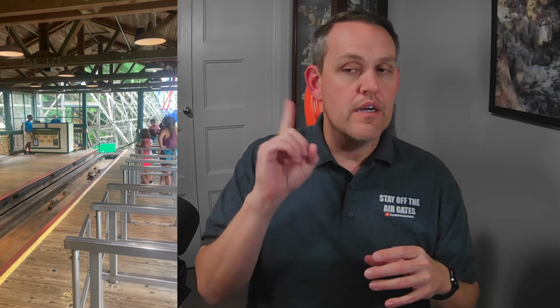Now, forces have their own special file where I go in and I could say, hey, my output for number 1 is a 0, and I simply install a force and I put a 1 in there and say, you're a 1 now, and then that output turns on. Now, in the processor's logic, there is a section for forces installed, and it says, okay, I have a force installed, and that section goes active.